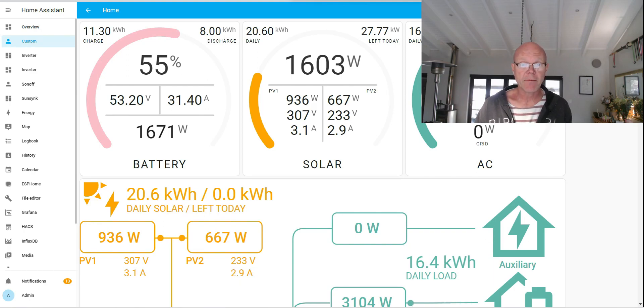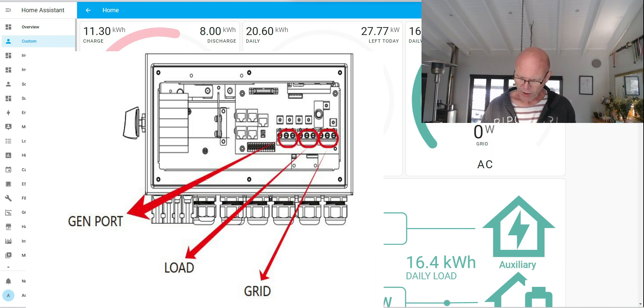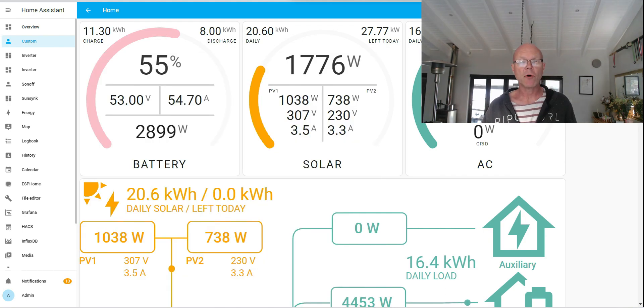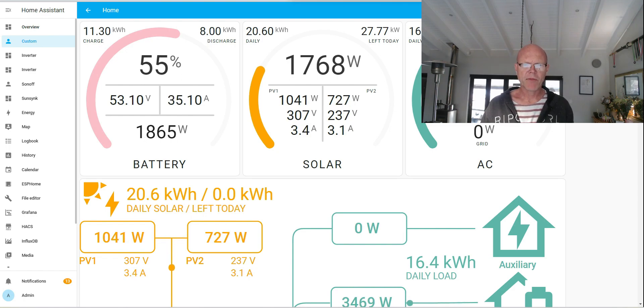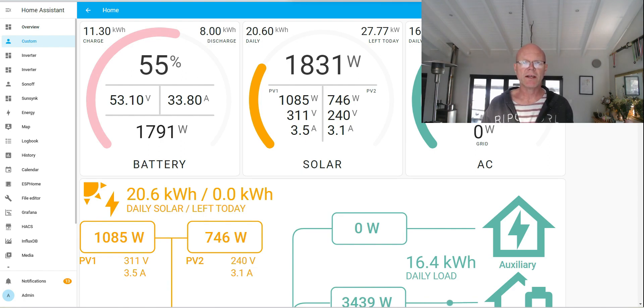There are two ways you can connect your generator. The preferred method is using the gen port or the auxiliary port on the inverter, and there are a number of reasons for this. First of all, it is much easier to restrict the amount of power being pulled from the generator — you set that in your auxiliary port settings, you can just set the maximum load. The second reason is that it ramps up the load on the generator a lot more gradually than the grid port does, and finally the allowed frequencies and voltage range is much wider on the gen port.